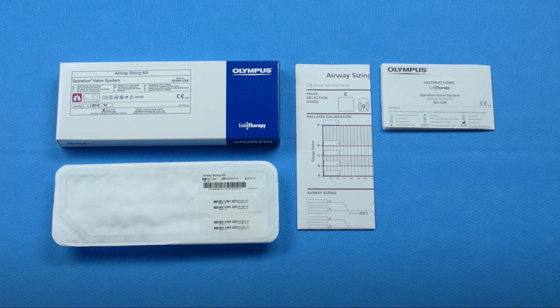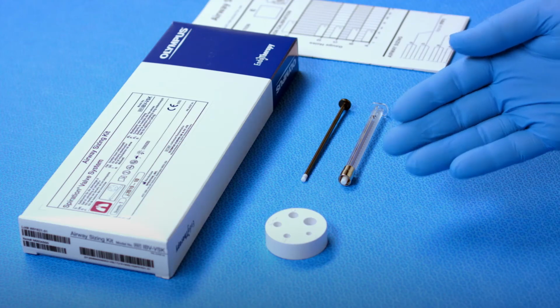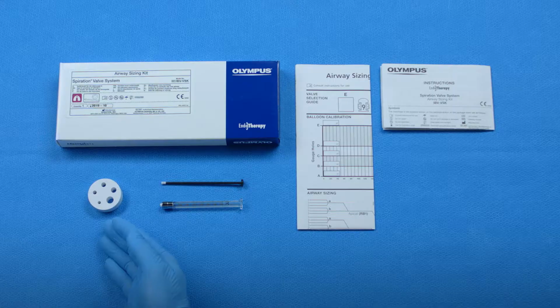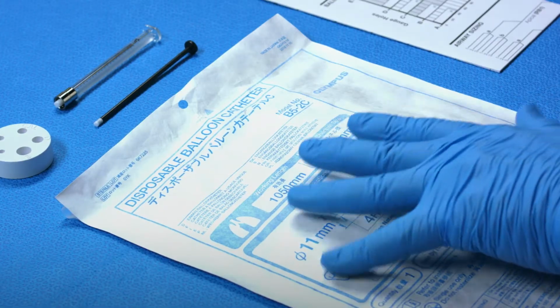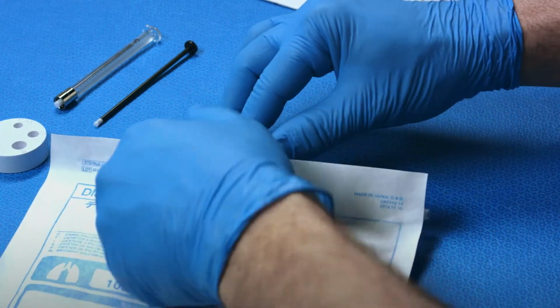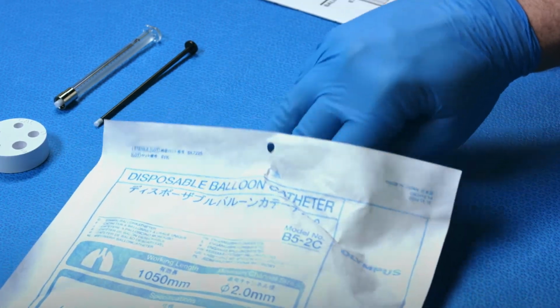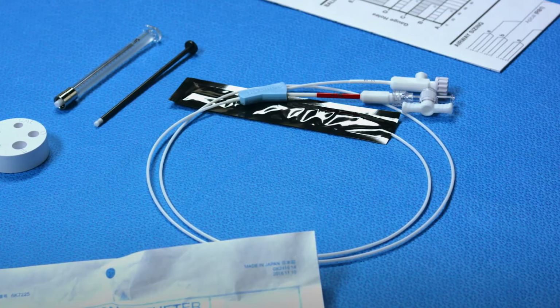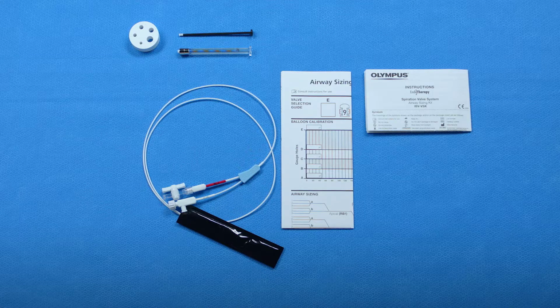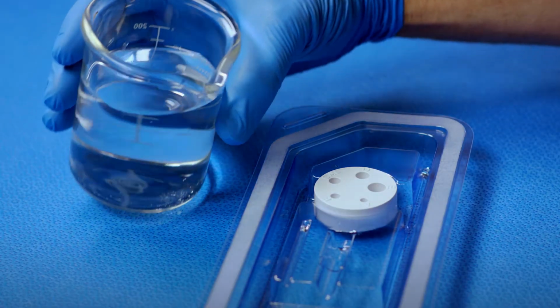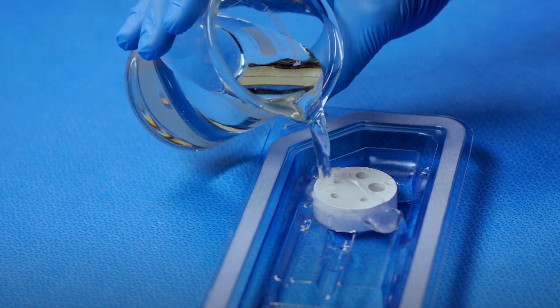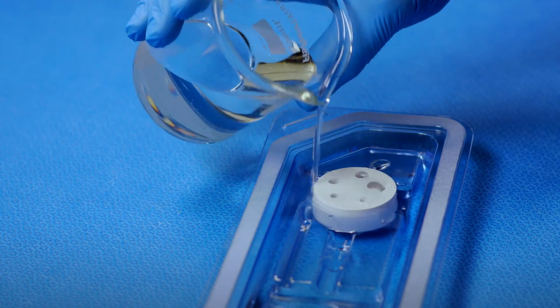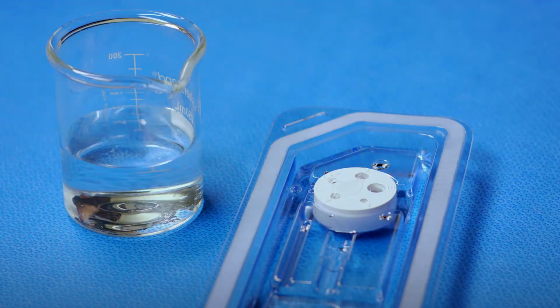The airway sizing kit consists of a glass microliter syringe, a calibration gauge, and a sizing worksheet. Once the Olympus B5-2C balloon catheter has been prepared, it will need to be calibrated. A worksheet is included to record the calibration data used for airway sizing. First, wet the calibration gauge and balloon with sterile saline and continue to keep wet during the calibration process.